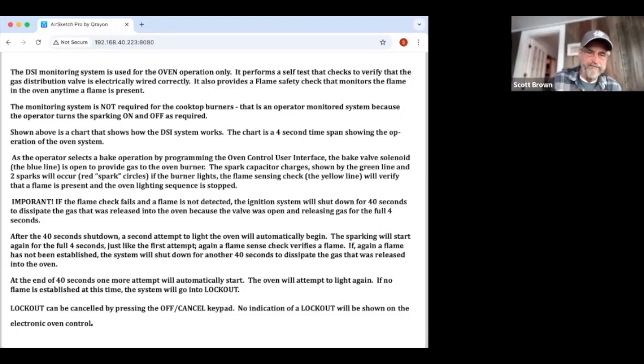And by the way, these DSI boards, Whirlpool doesn't make them. They buy them from another manufacturer. And so it's a standard J1 connector, and this algorithm of operation is typical of all DSI boards. And DSI is really not that mysterious. A lot of guys get intimidated by it, but if you've worked on car ignition systems, it's kind of the same thing with just a few extra features, flame sensing, for example, and this algorithm of running for 4 tries and then cutting out. But you've got an ignition coil.